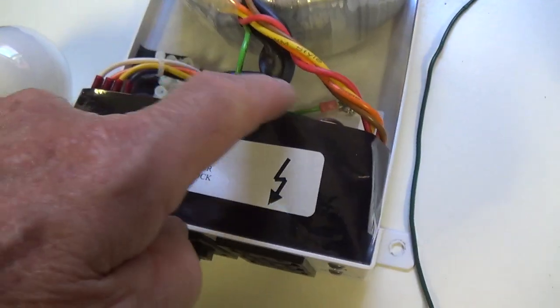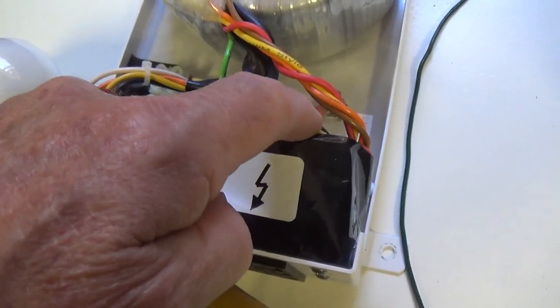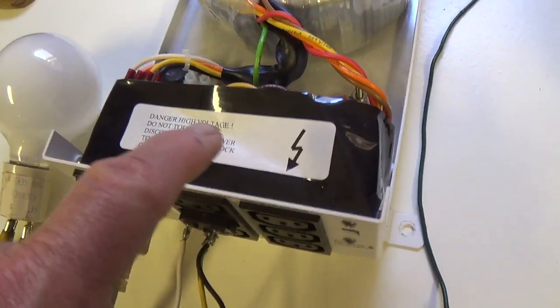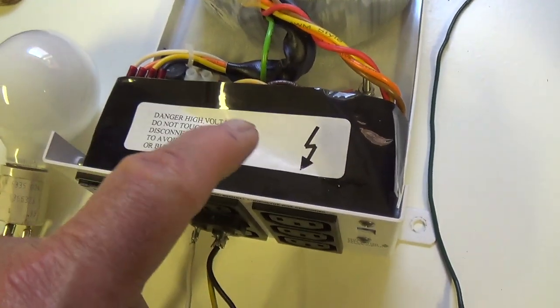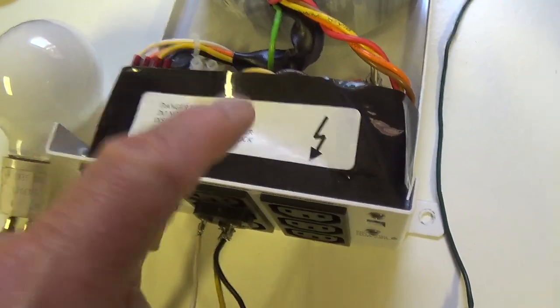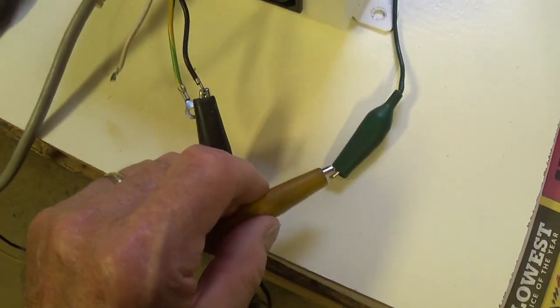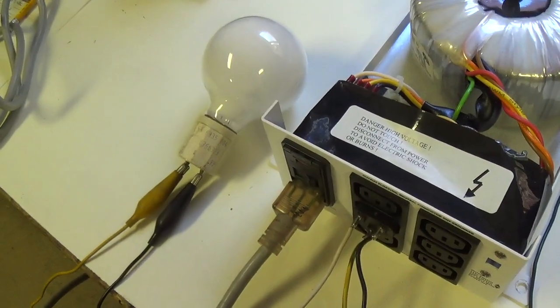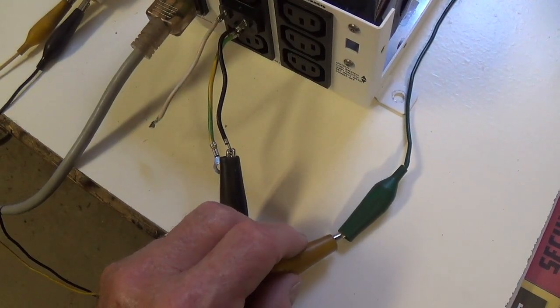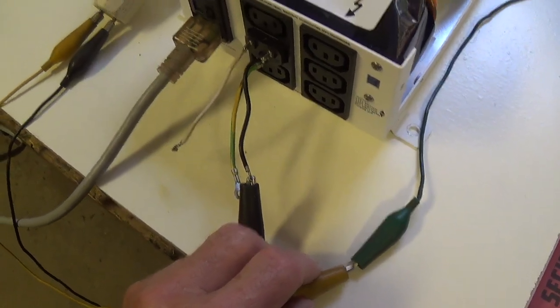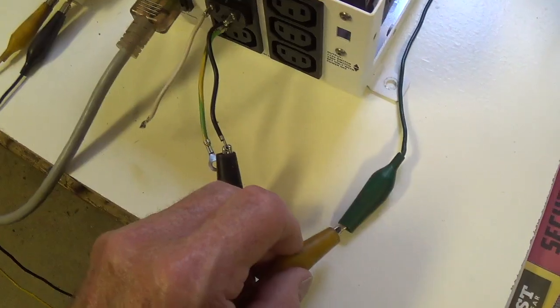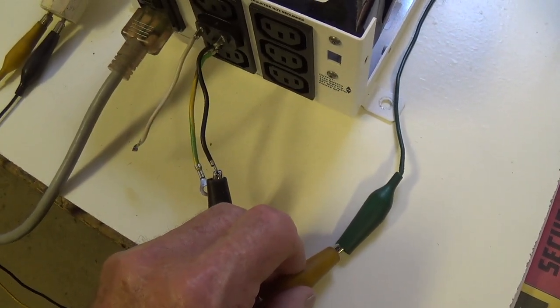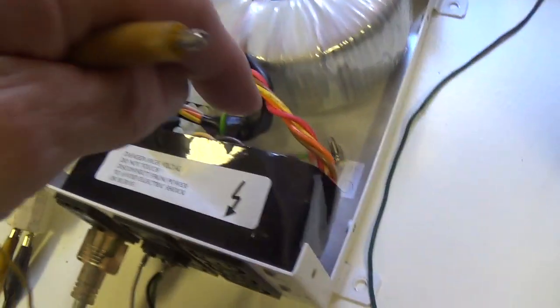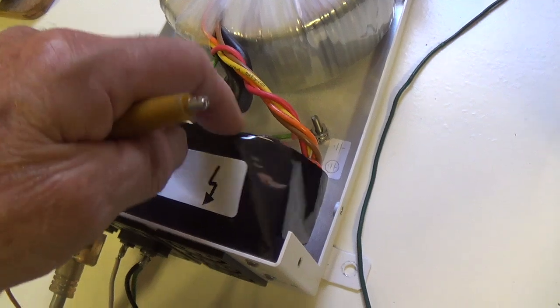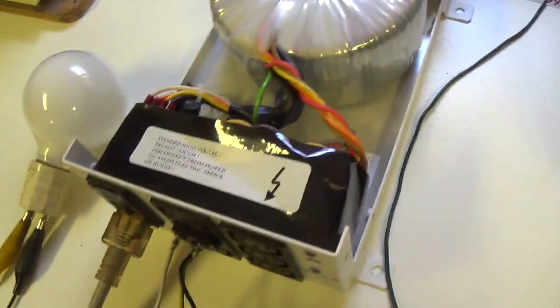Now, what would have happened if you had left your return wire on your medical grade isolation transformer connected to ground? Okay, if you had the type of isolation transformer that's really just to isolate from electrical noise, not from ground reference, if you touch it to this piece of metal, it would illuminate the bulb. So my suggestion is, if you're not sure about your isolation transformer, test it this way. If you touch the metal here that is the ground lug of the AC receptacle and this lights, you're going to have to go into your isolation transformer and unground that common return wire.